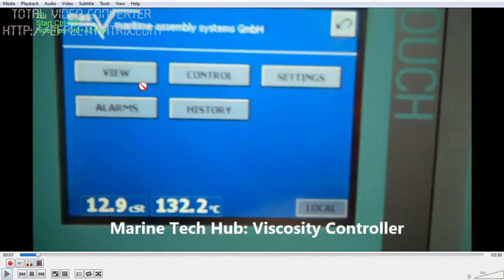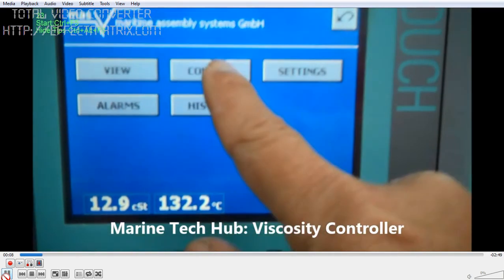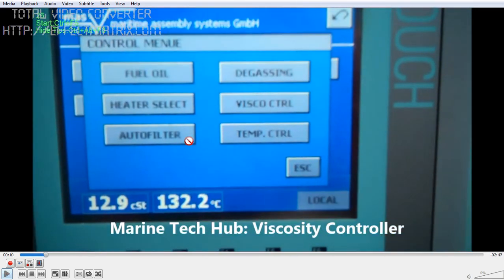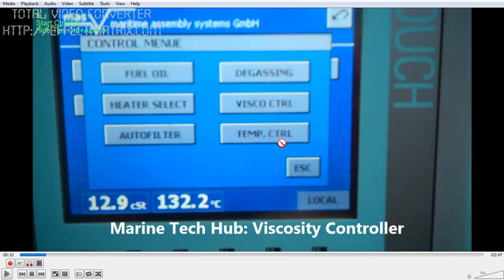We have a control panel here. You can see this is the control, alarms, view, history, and settings. Once I press the control, you have fuel oil, heater selection, autofilter, then degassing, viscosity control, and temperature control. So in viscosity control, if the viscosity sensor is working, it will give a signal to the steam valve to control the steam to maintain the viscosity.